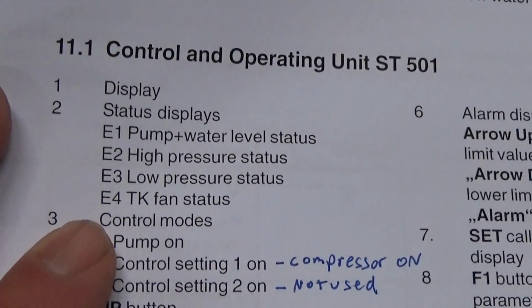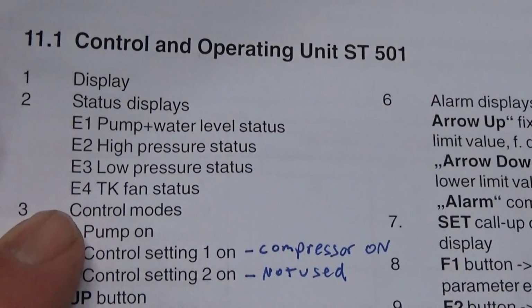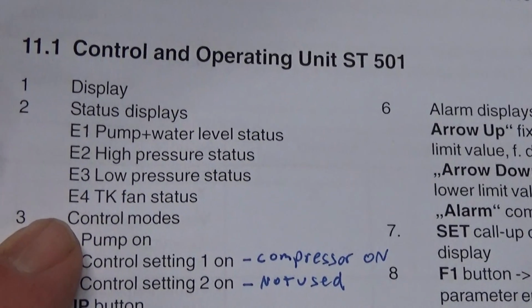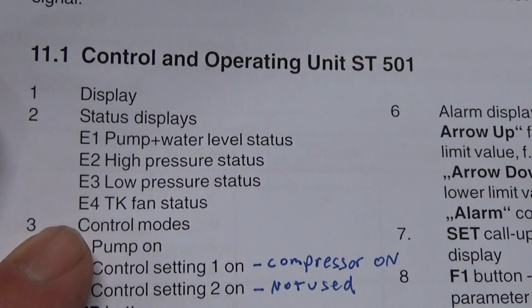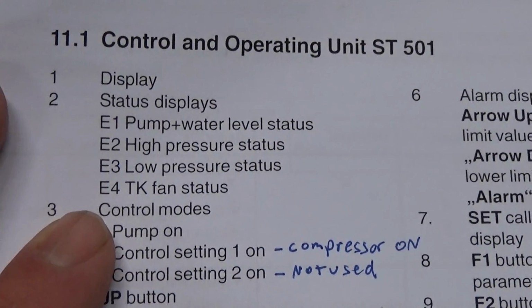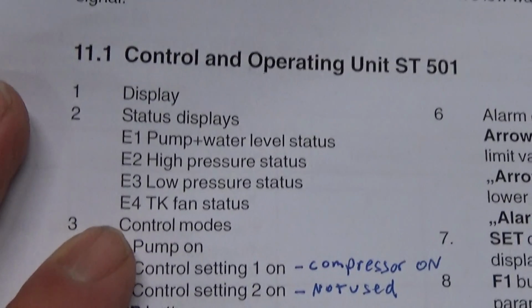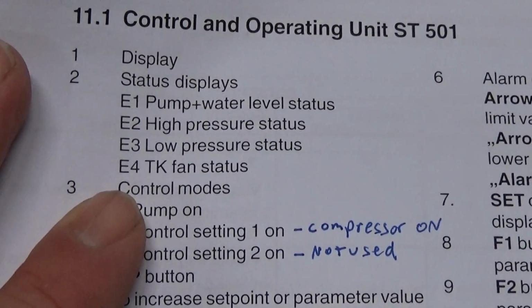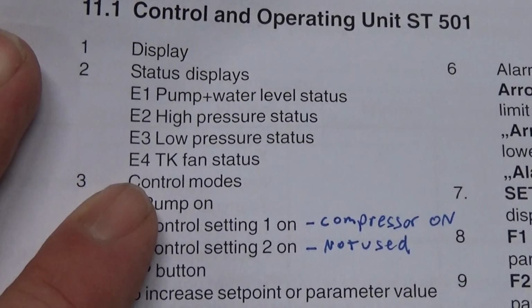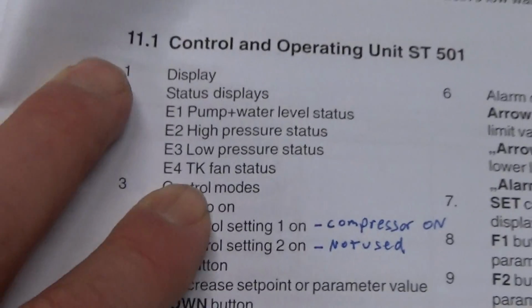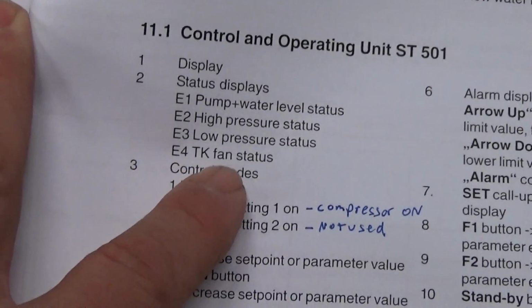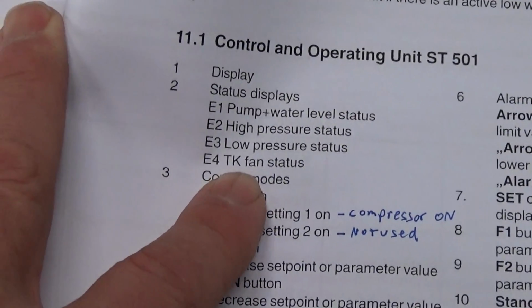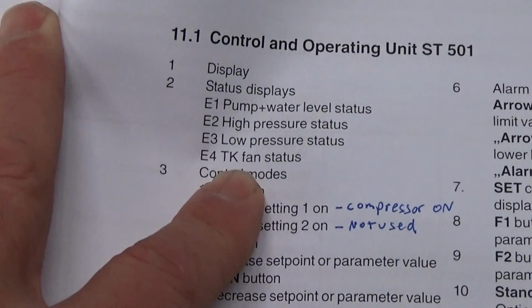That's normal. E2, high pressure. So when the light's on, that means it's behaving correctly. When it's off, that means there's a problem related to the high pressure refrigerant alarm. E3, low pressure, and E4, TK or fan status. That will go off if there's an error related to the fan, or if the compressor shuts down, because that's related to the fan too.